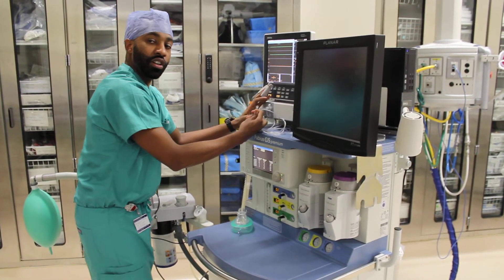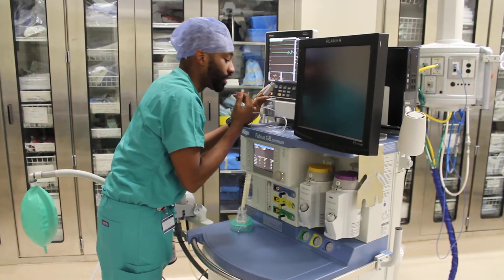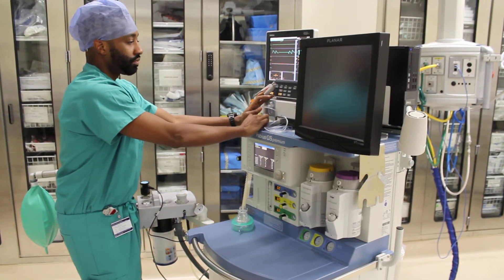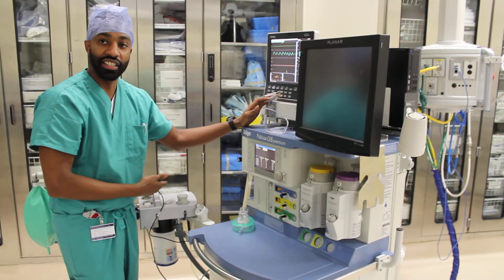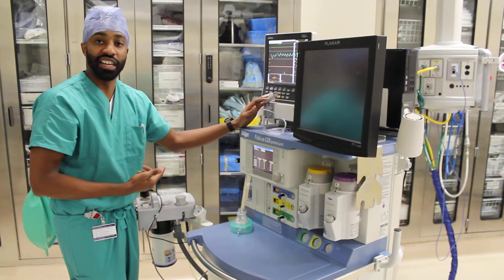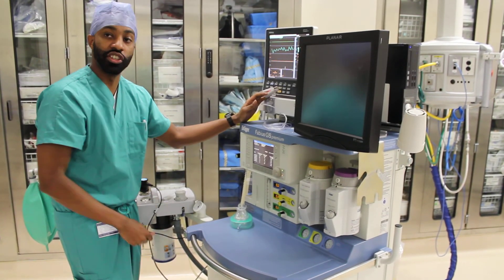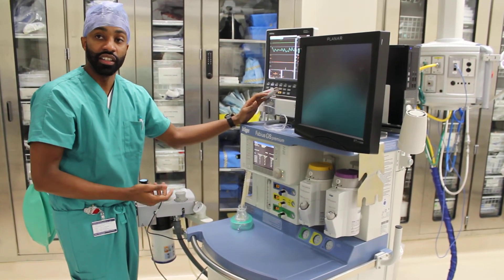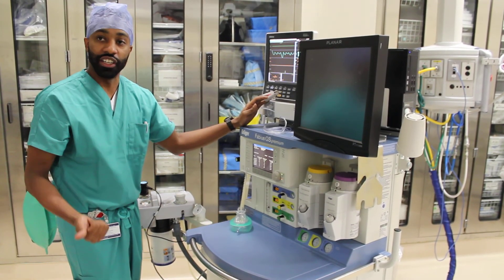In order to see our end-tidal CO2, all you have to do is breathe and blow on top of the CO2 and you should see a waveform. Once that is complete and you see the waveform and the leak test is finished, that is the best time to check your hypoxic mixture between your nitrous and your oxygen — you should not be able to create that. In order to see that test go through in its entirety, follow us on the next video.